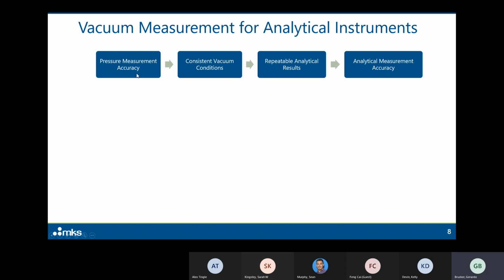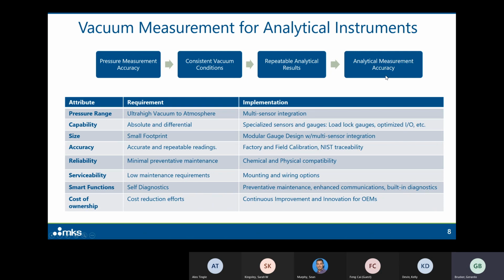In reality, any one of these instruments that does analytical measurements depends on accurate pressure measurement in order to deliver accurate analytical results. That's why the quality of the gauges that you put in your instruments is so important. But accuracy is not all there is to it. Looking at the needs of the analytical industry, there are a lot of things that analytical chemists worry about when it comes to their vacuum needs.